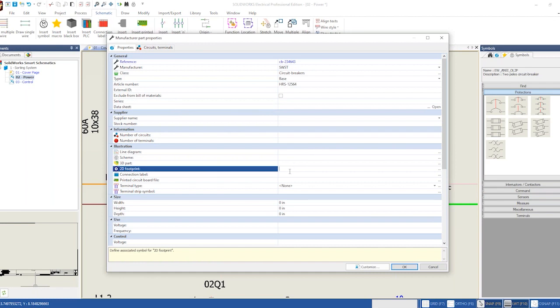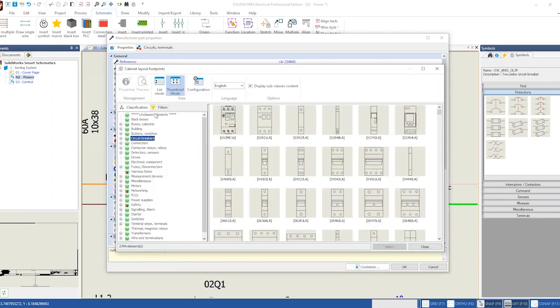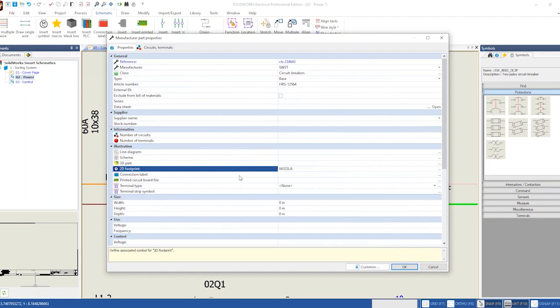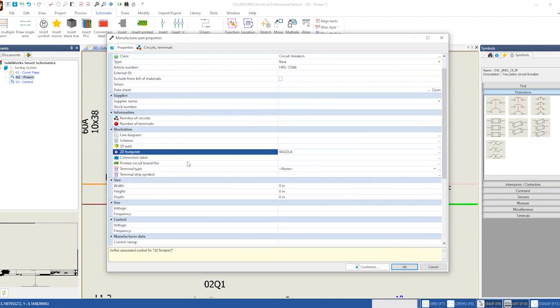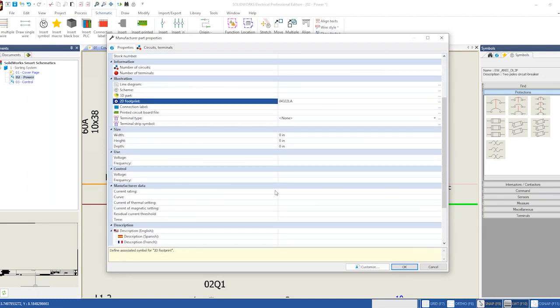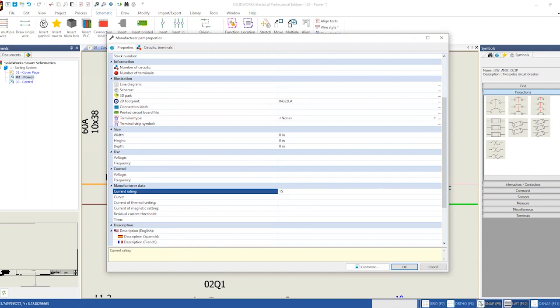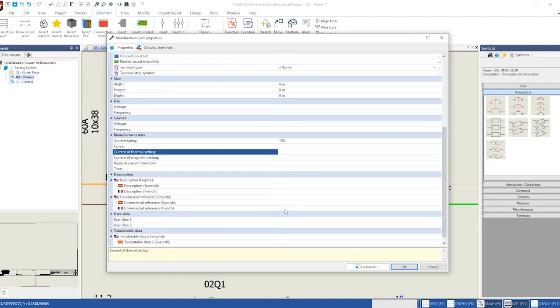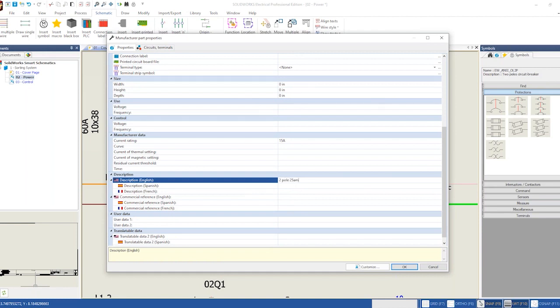Now, one of the things I might want to do is define a footprint symbol for this. What type of circuit breaker is it? It's a 2-pole circuit breaker, so I can simply select that one as a 2-pole circuit breaker to use. Other things I might want to insert, say current rating: this is a 15 amp circuit breaker. If I knew the curve, the thermal settings, whatever that might be, I can define that also. Description: 2-pole, 15 amp.